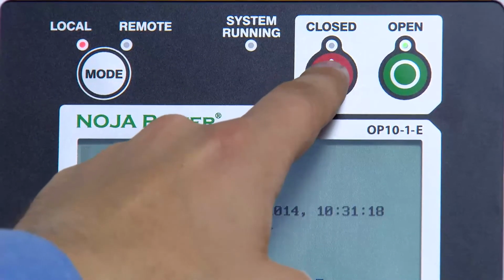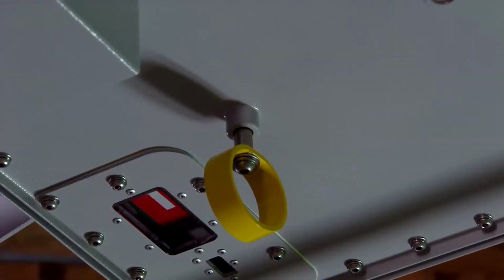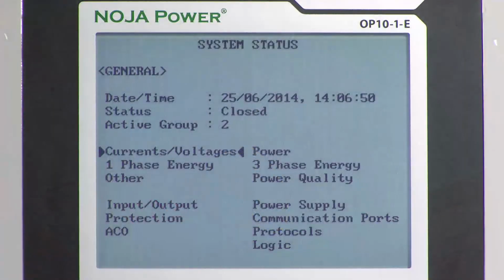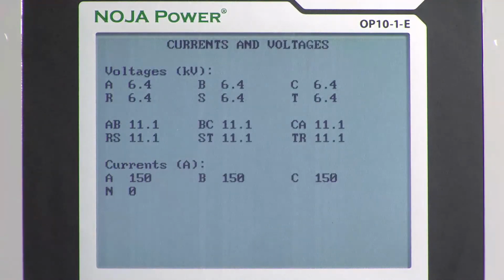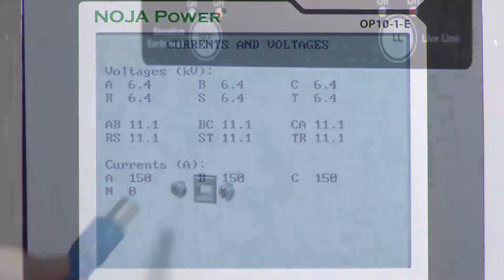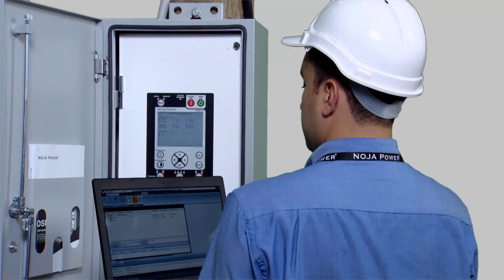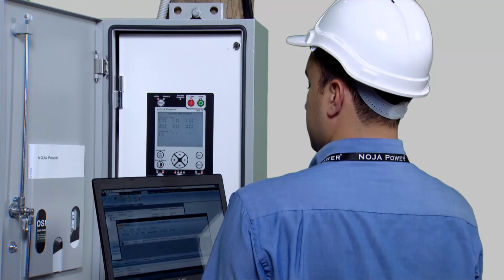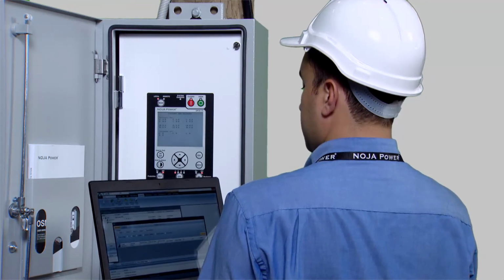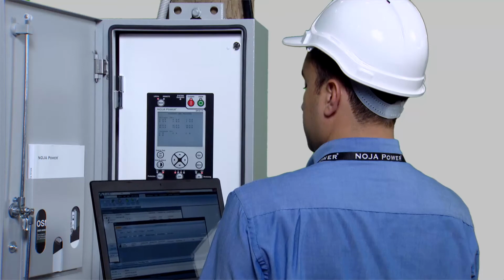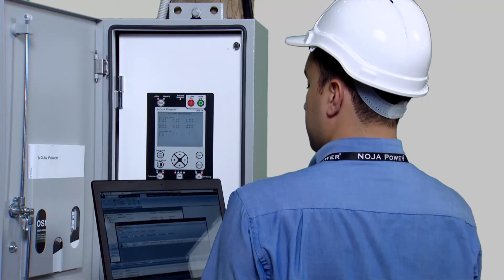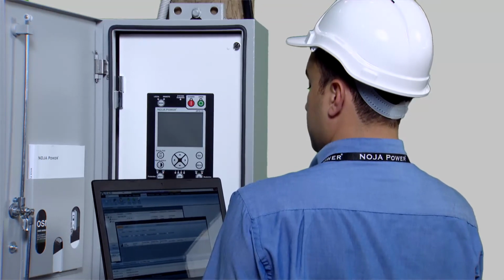If possible, conduct some manual trip and close operations from the panel to confirm operation. If the feeder is energized, check that the voltage and current readings on the panel are correct. Connect to the RC10 with the CMS software package and load settings as required. Conduct any other commissioning tests as specified by local regulations and requirements.